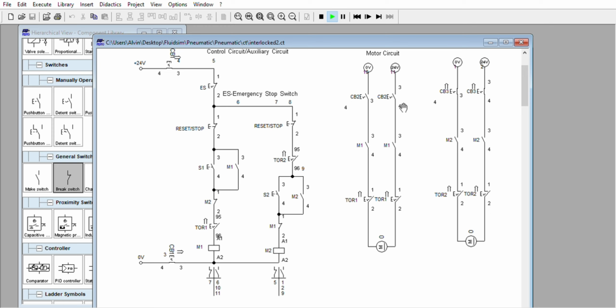So what to do? We are going to turn off the circuit breaker. Do not reset the overload relay. In actual, you don't have to reset that one because there are troubles within the system, within the motor, because there is overcurrent, because this is tripping. So do not reset that one, but turn off the circuit breaker immediately.